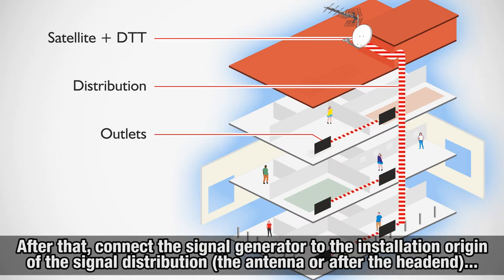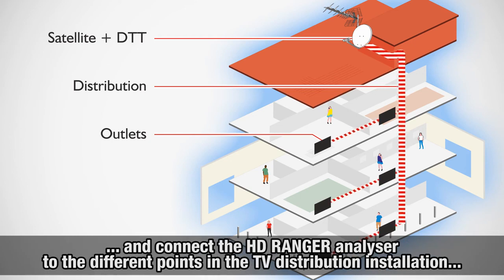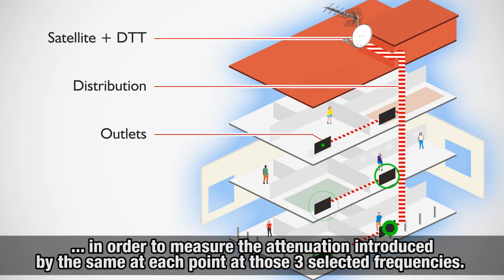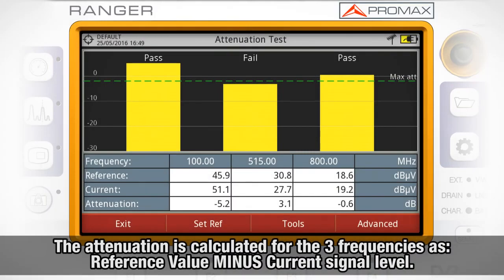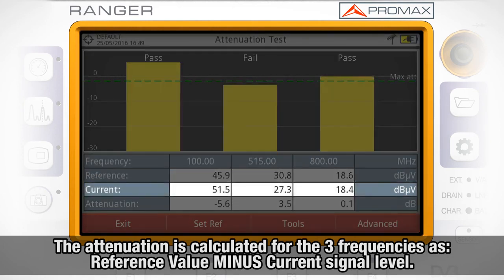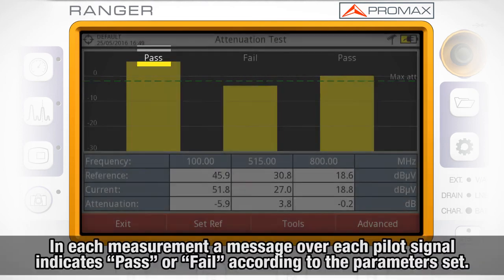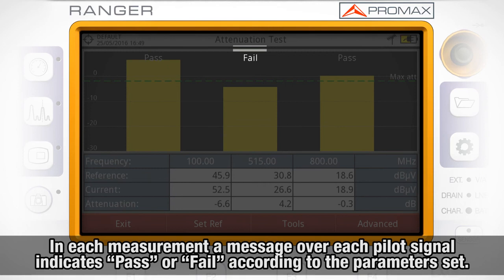After that, we will connect the signal generator where the origin of the signal distribution is in the installation, that is, after the antenna or after the headend, and connect the HD Ranger analyzer to the different points in the TV distribution installation in order to measure the attenuation introduced by the same at each point at those 3 selected frequencies. The attenuation is calculated for the 3 frequencies as the reference value minus the current signal level. In each measurement, a message over each pilot signal indicates whether the measure passed or failed according to the parameters set.